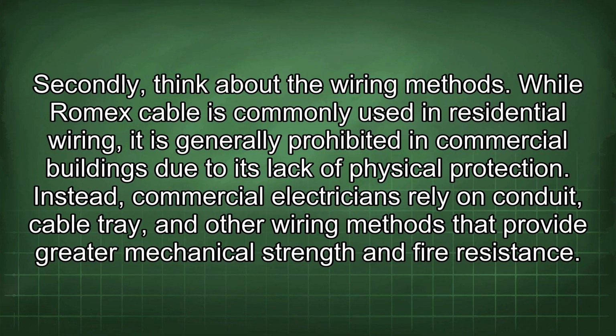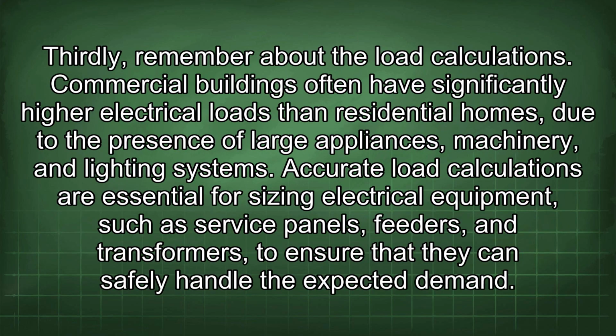Secondly, think about the wiring methods. While Romex cable is commonly used in residential wiring, it is generally prohibited in commercial buildings due to its lack of physical protection. Instead, commercial electricians rely on conduit, cable tray, and other wiring methods that provide greater mechanical strength and fire resistance. Thirdly, remember about the load calculations.